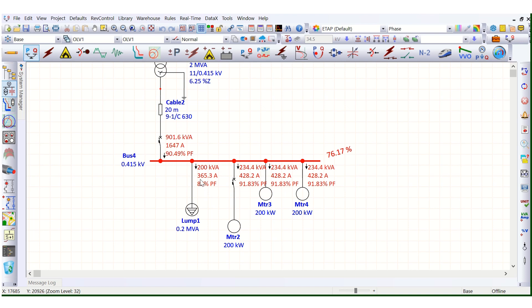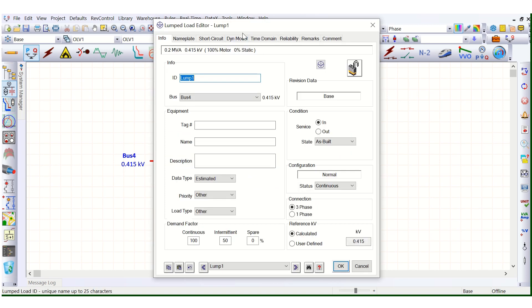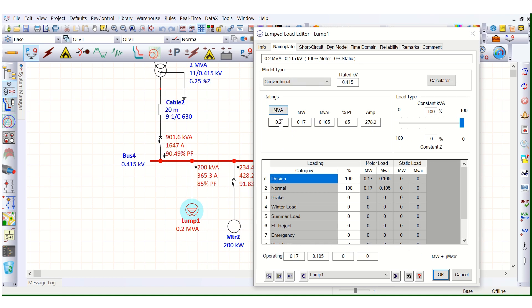Running the load flow, the 0.2 MVA lump load is drawing 365.3 amps and the bus voltage is coming at 76.17%. However, the rated ampere for this 0.2 MVA load is 278.2 amps. So why is it drawing 365.3 amps?